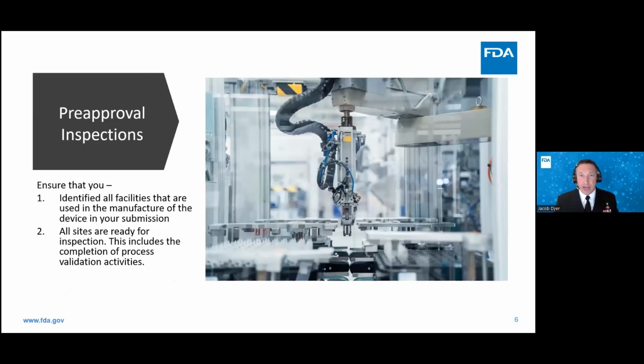As I mentioned before, FDA utilizes pre-approval inspections to determine that the device and the manufacturing facilities, methods, and controls are in place. And I say it's very important to, when I say in place—everything else was reviewed based upon documents coming in, and oftentimes it's some of these validation activities, especially process validations, this is what we're going to do. But by the time the inspection comes, they have to have been done, and it needs to be in a fully operational environment.